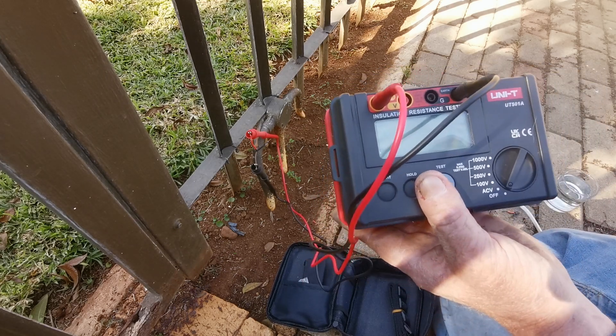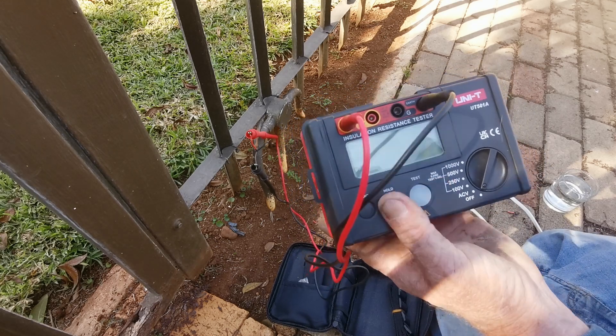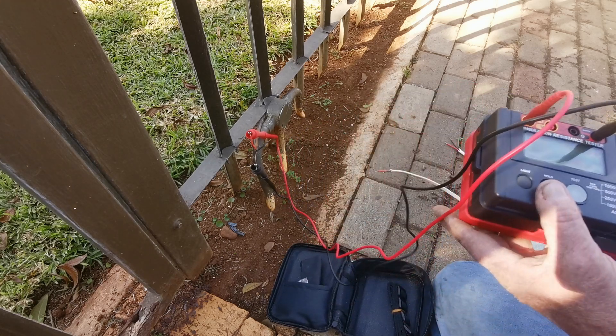This is why you cannot rely on a multimeter to test for damaged cable — because this only puts out one volt, whereas the insulation tester puts out 500 or a thousand volts. That is why this piece of kit, the UNI-T UT501A, is very very useful. A multimeter has its own uses, but this is a very simple, very easy to use piece of equipment.